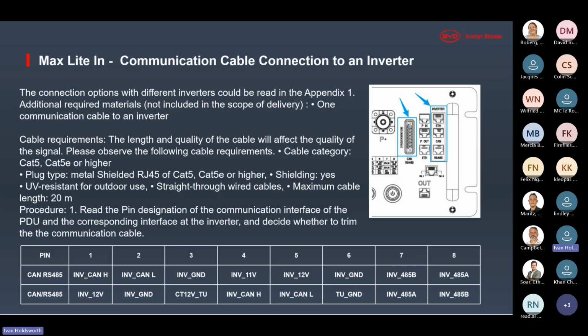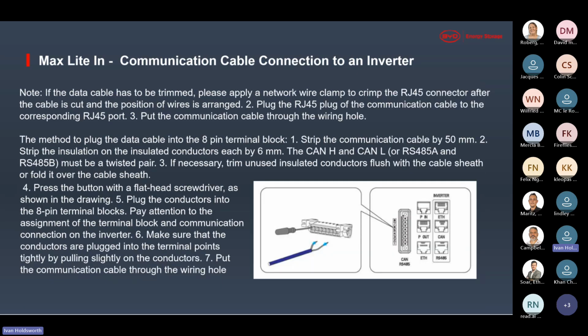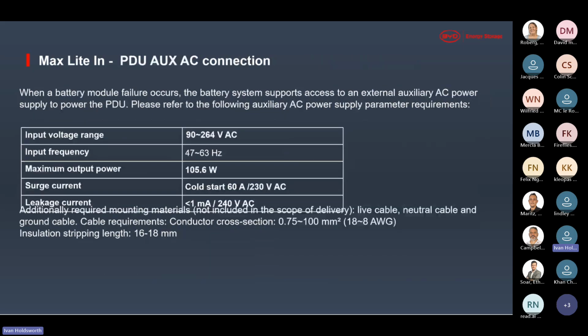And you can see the communications. You can either connect on a wire connector or on an RJ45. Those are connections to your inverter, and your inverter connections can also be TCP/IP over Ethernet. And there's various different other communications that can be used, but almost always it's CAN high and CAN low to your inverters. And here we can see how to connect on the wire connectors.